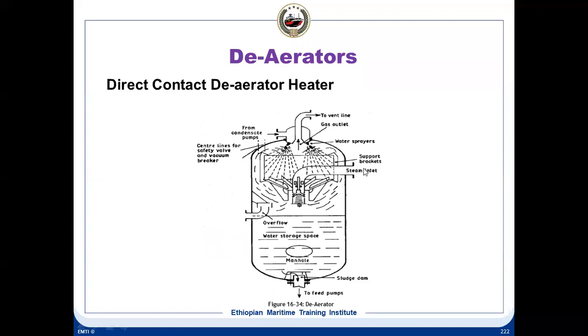And then from a small steam tapping which is coming from the turbine, the heat from the steam is given to this feed water, so that the feed water temperature increases very rapidly, due to the fact that it is broken up into a very fine spray. The surface area is greatly improved. And the heat is transferred from this incoming steam. The steam requirement here is not much. It is just to heat up the feed water.